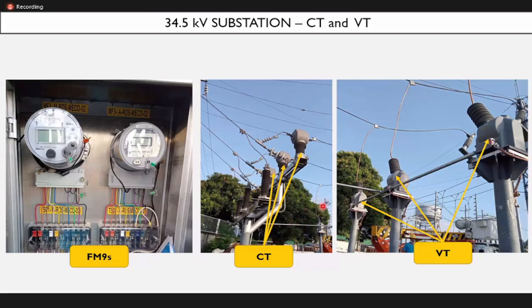For the substation 34.5 kV, this is the primary metering voltage transformer. Actually, ang talaga pong term is VT or voltage transformer. Nasanay lang po kami na pag sa primary metering na 34.5 overhead and vault type, ginagamit po namin yung term na PT or potential transformer. Pero sa mga substations po, we use VT. And it's just the same po. This is the CT. And these are the Form 9S meters. The left side is the main meter and the right side is the backup meter.